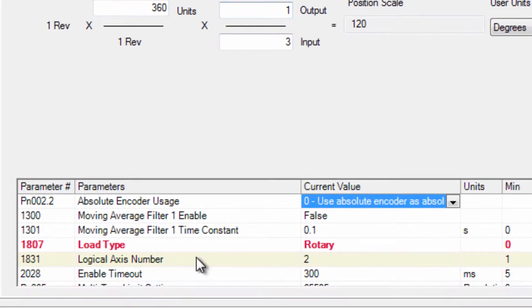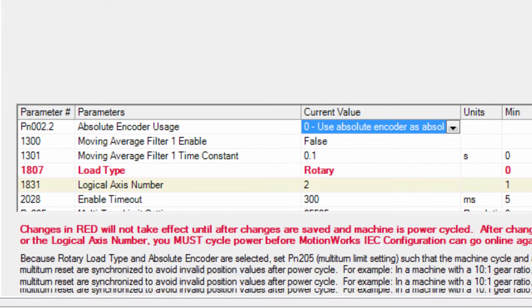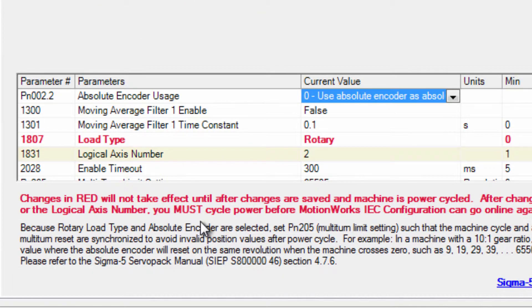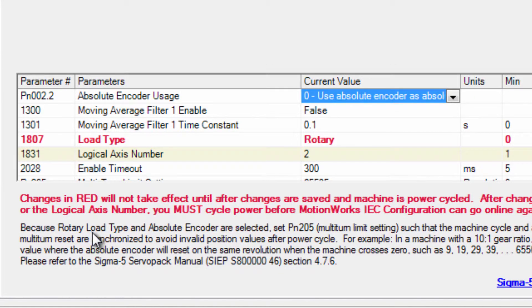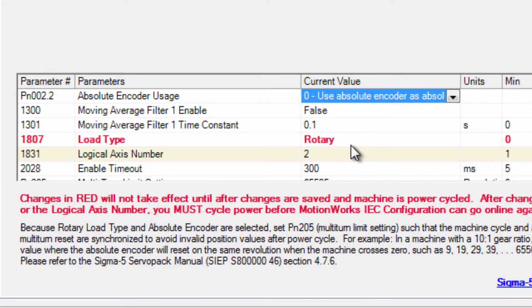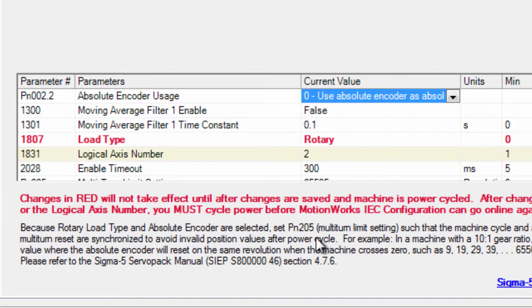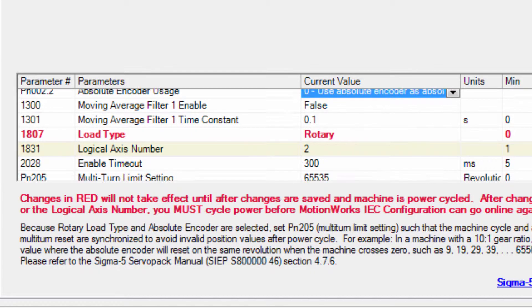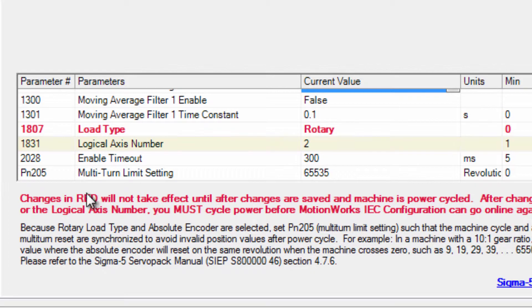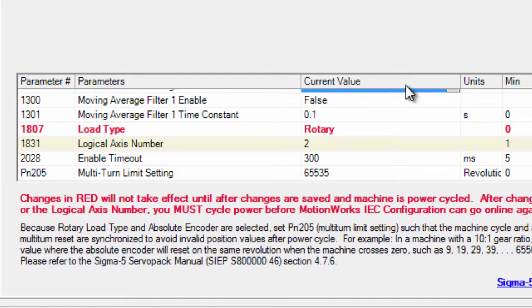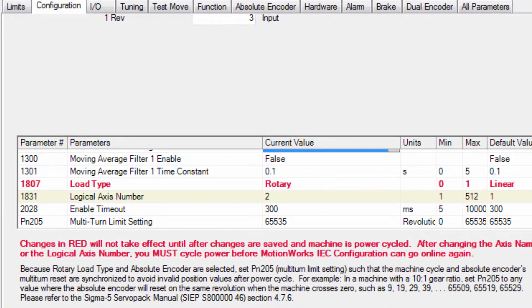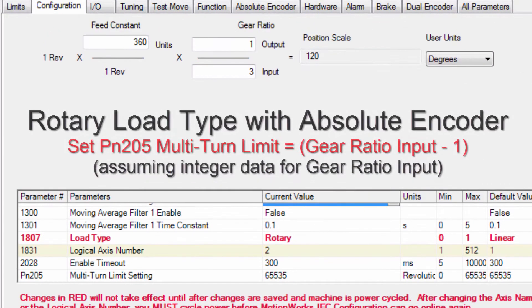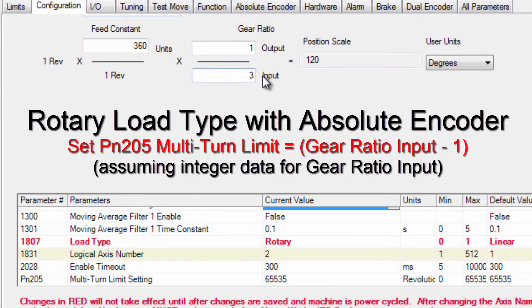You might have noticed the red text which if you scroll down it reminds us that we need to save and cycle power for the changes to take effect but also you see a note below which says that the combination of absolute encoder and rotary load type requires setting the encoder multi-turn limit PN205 and you can look down here PN205 multi-turn limit setting.